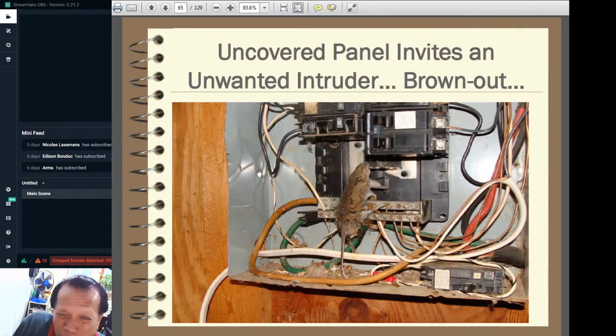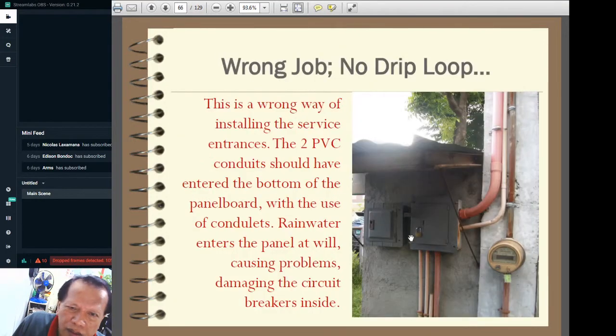Okay, so panel board should be provided with cover so as not to allow foreign bodies like this animal to enter and cause problems. No, this animal bit the bus bar here, and then he's grounded. See, so very dangerous. And of course, proper installation of conduits. This is not the correct way. When it rains, water would enter the electrical panel, and it would also cause electrocution of somebody that might touch the cover when it is wet. So that is an incorrect way of installing the panel.